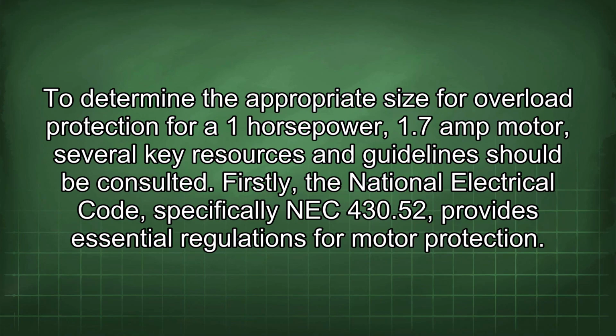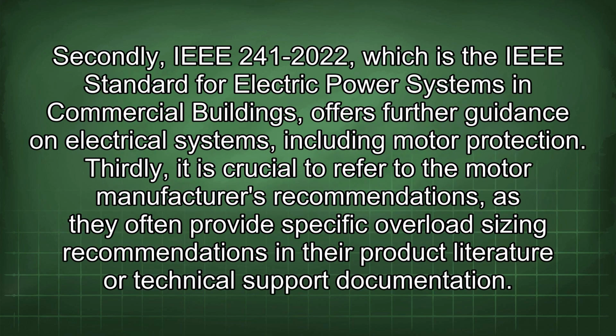To determine the appropriate size for overload protection for a 1 horsepower, 1.7 amp motor, several key resources and guidelines should be consulted. Firstly, the National Electrical Code, specifically NEC 430.52, provides essential regulations for motor protection. Secondly, IEEE 241-2022, which is the IEEE standard for electric power systems in commercial buildings, offers further guidance on electrical systems, including motor protection. Thirdly, it is crucial to refer to the motor manufacturer's recommendations, as they often provide specific overload sizing recommendations in their product literature or technical support documentation.